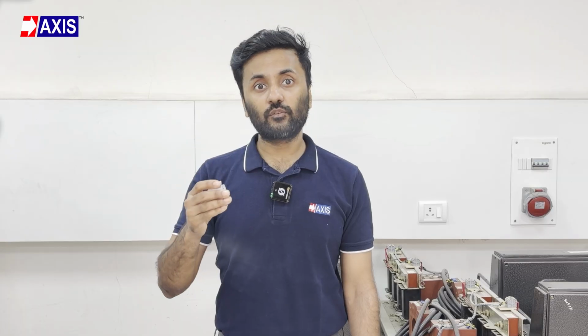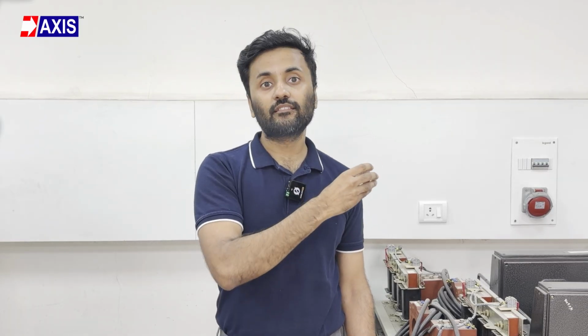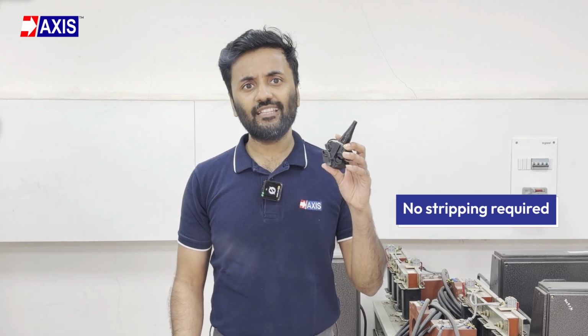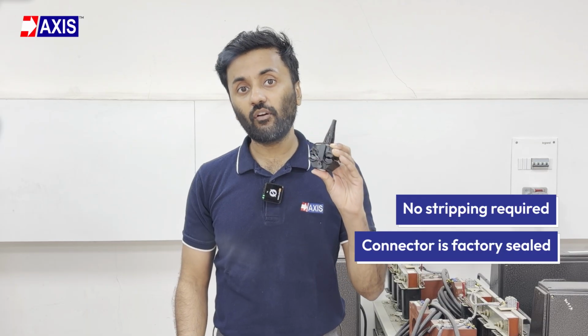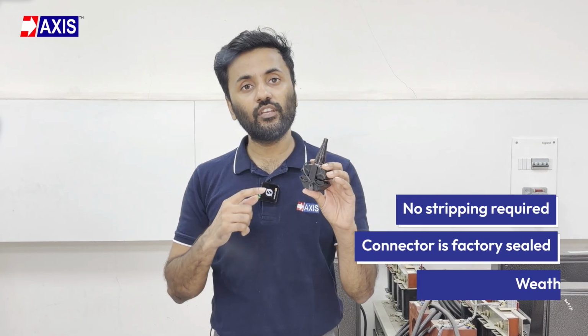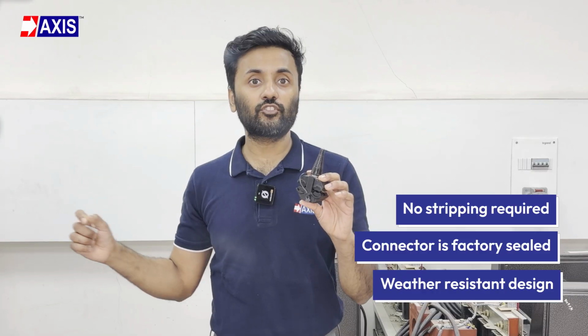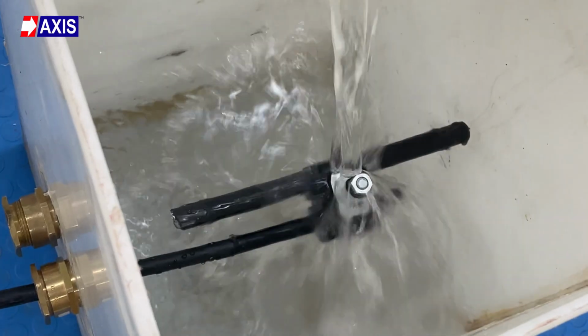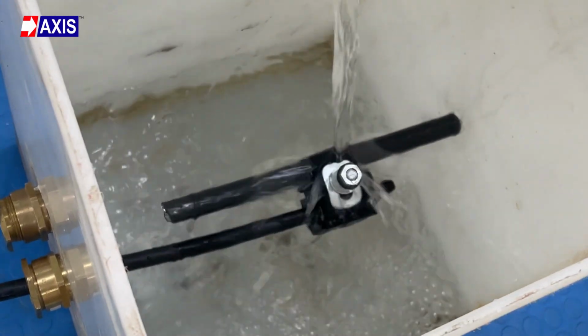Once water enters through the seal, it reaches the stripped section of the cable, and water travels along the conductor strands. The cable insulation is now breached from the inside. The cable starts to fail. You cannot see this happening from the outside, but by the time you detect the problem, your cable is already damaged. With an IPC, there is no stripping. The insulation stays intact, and the connector comes sealed from the factory. The housing that is made of reinforced plastic resists weather conditions. The entire assembly is waterproof with no exposed cable and no entry point for water.